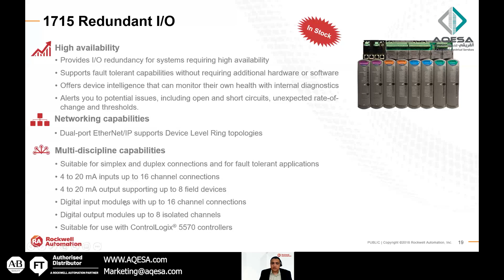Okay, the integrated condition monitoring. Again, this is a little tricky because these are somehow IOs, because you add them to the ControlLogix or CompactLogix IO tree, and they are monitored by the ControlLogix or CompactLogix CPU. But for API 670 compliance, we need these controllers to be such that if you disconnect the cable between this module and the Logix CPU, the protection against vibration is still there. Unlike, let's say, an RTD module or digital output or analog output, if you lose communication between the IO module and the CPU, you don't have any protection or any readings. You have a fault, okay? But this one is not like this, because this is an API 670 compliance issue.